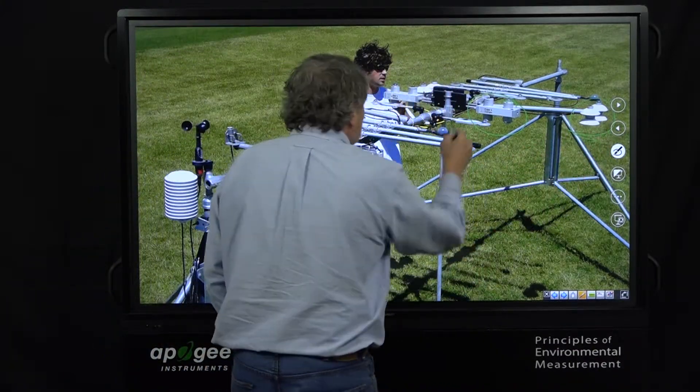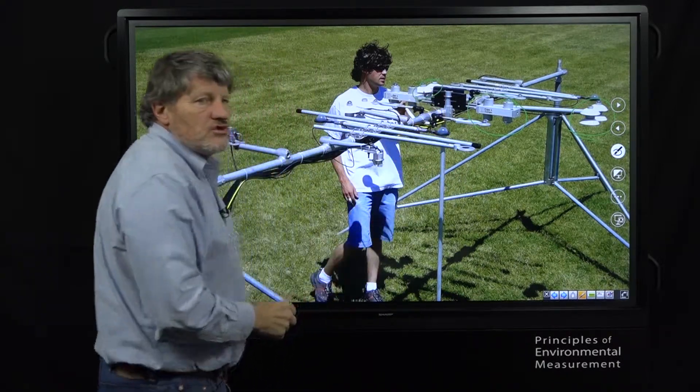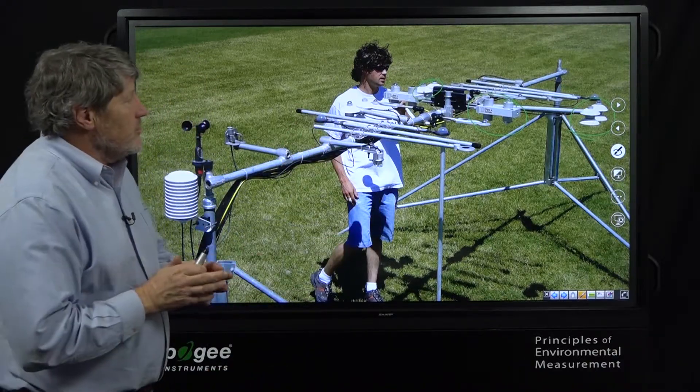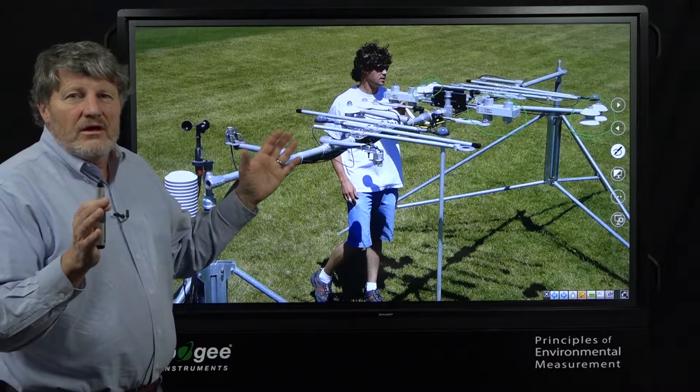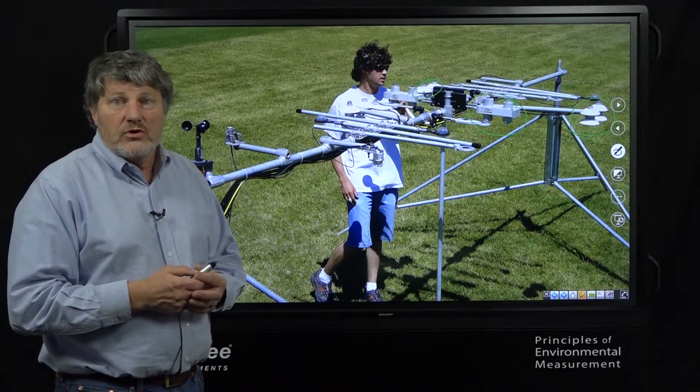If we look hard in here you can see triplicates of all these sensors on this mast. We ran this all summer long, collected an enormous body of research and concluded if we're going to do a good job in net radiation we need a four component instrument.